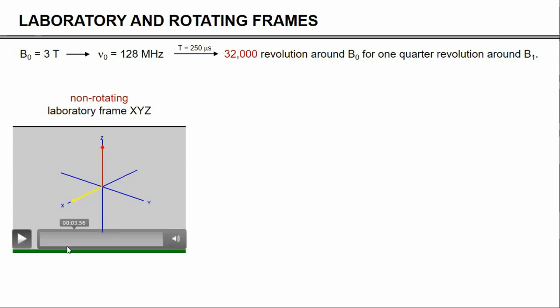Okay, so now we need to talk about rotating frames. So let's say that we are at a magnetic field of 3 tesla, which then corresponds to a Larmor frequency of about 128 megahertz. So let's say that we consider the pulse from the previous slide that had a duration of 250 microseconds. In that time, the spins revolved 32,000 times around B0, but they only revolved 90 degrees, or a quarter of a revolution, around B1. So if you visualize that, you get something like this, where the magnetization is in red along the z-axis, and the B1 is yellow, and the B1 will, of course, rotate at the Larmor frequency.